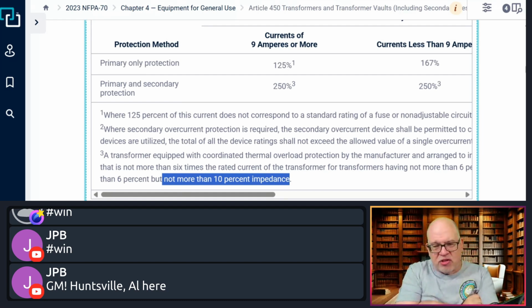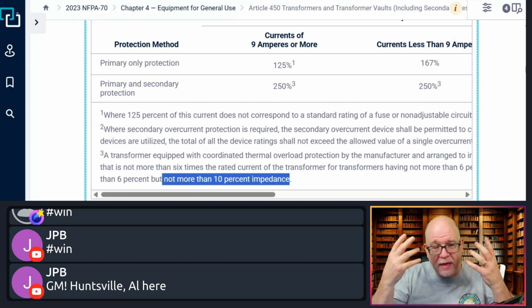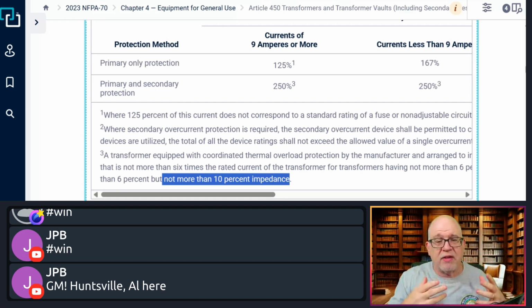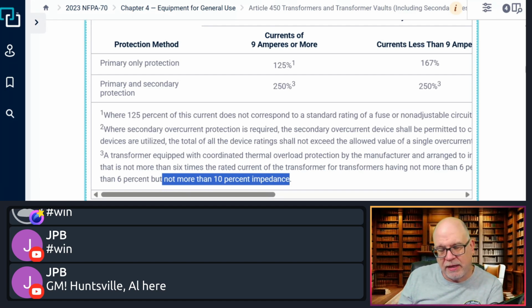Now, why would I ever have a 250% primary? Well, maybe that transformer has a secondary that's coming off with taps from it. Secondary conductor taps that supply multiple transformers. And the collective inrush that would come from supplying multiple transformers, we want to make sure that it doesn't trip out the actual transformers. So under those scenarios, you can go up to 250% on the primary side, but you can't exceed it except where note 3 says, based on those conditions, because those unique transformers have built-in components that protect them, okay? That's the only time.